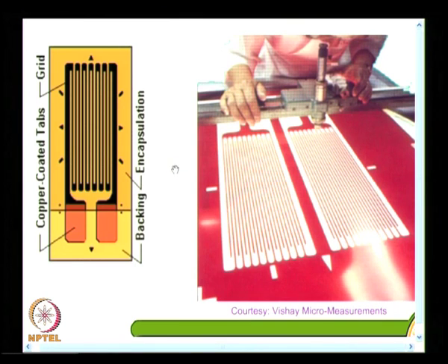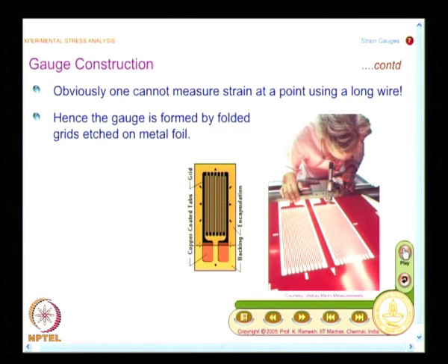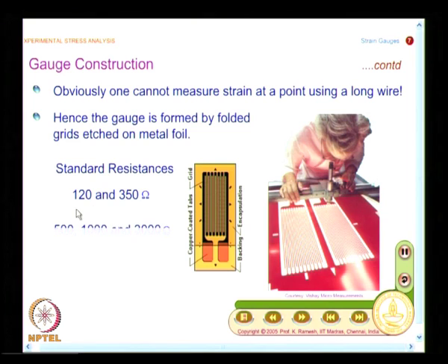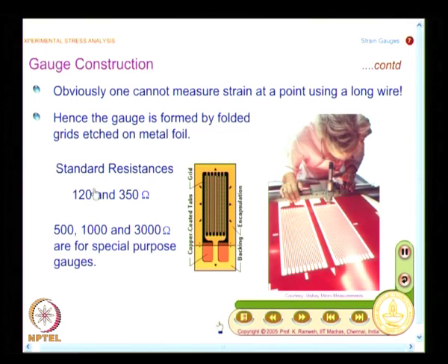And we will now see what are all the resistances that are available. You do not have it as 100 ohms, the base is 120 ohms. This is from measurement consideration. For our discussion, to alert that you need a long wire, I said let us start with 100 ohms, but the least resistance that is commercially available now is 120 ohms.